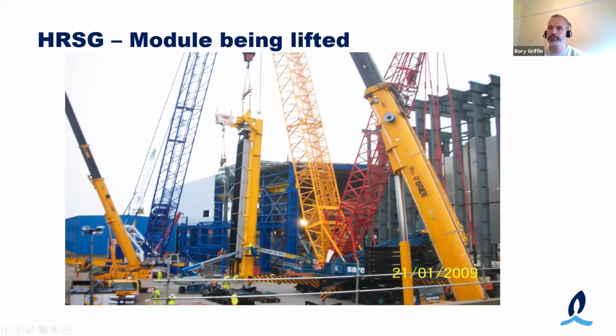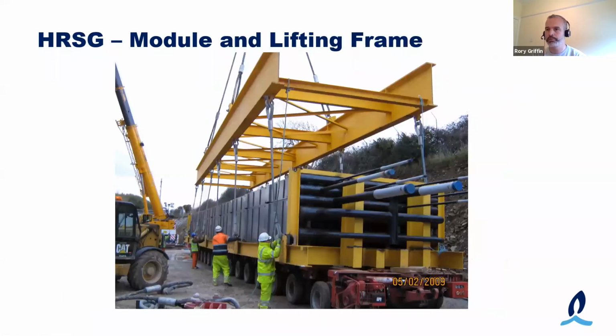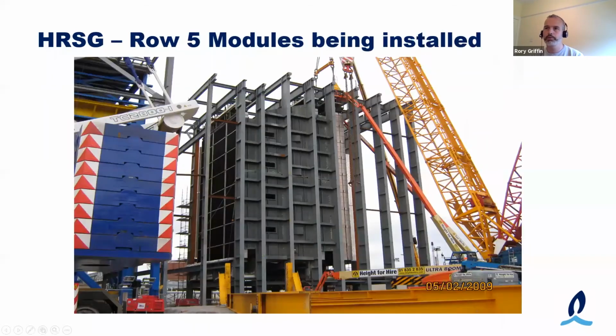Just moving on to the next picture here. It's a closer look at one of the modules. So in here, you can see the tubes that would be, you know, vertically in the boiler, and then you have connections. I'm not sure if that's the drain end or the end that connects up to the drums, but at each end there's connections to, you know, to complete the connections, I suppose. And here we have module 5 being lifted into place. So the duct burners are situated here after the superheater 3 on the HP circuit.